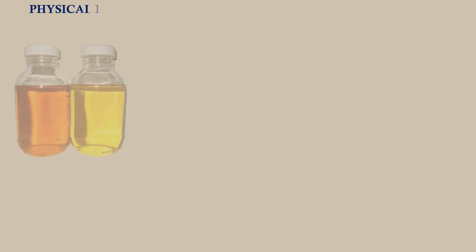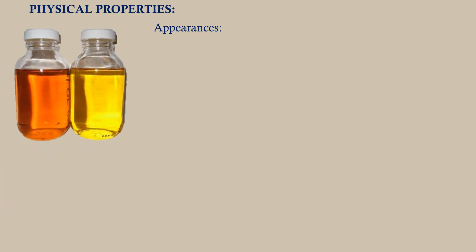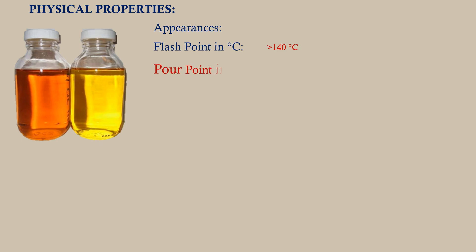Physical properties — Appearance: the transformer oil will be clean, transparent, and free from suspended matter or sediments, and free from acidic smell. Flash point in degree centigrade: a high flash point of transformer oil, more than 140 degrees centigrade, is desirable to minimize the chance of fire hazards.